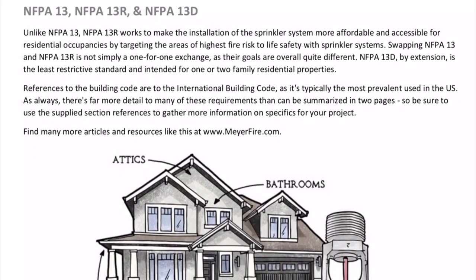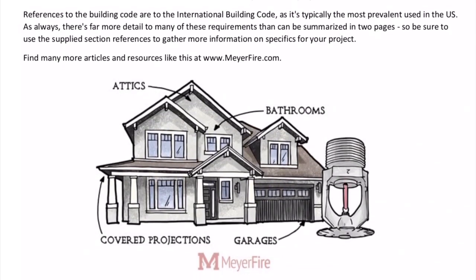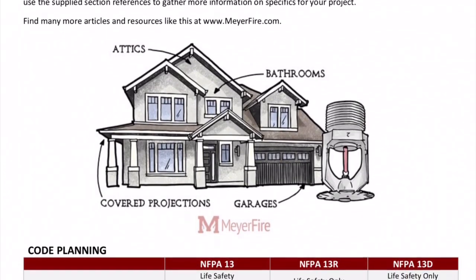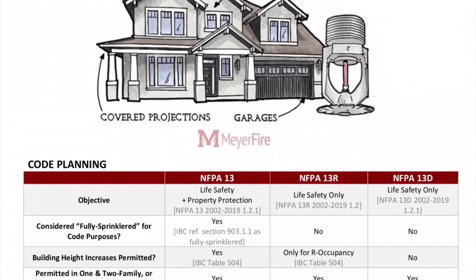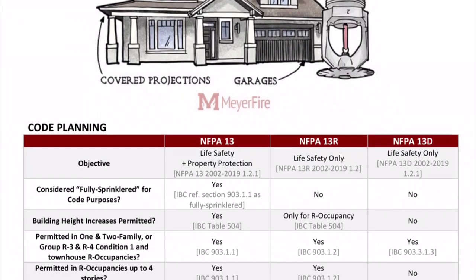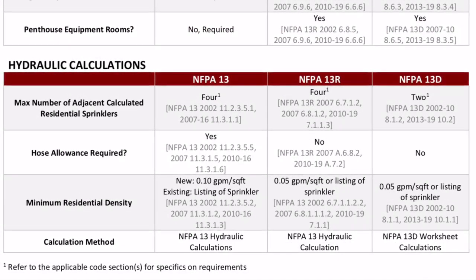Unlike NFPA 13, 13R works to make the installation of the sprinkler system more affordable and accessible for residential occupancies by targeting the areas of highest fire risk to life safety with sprinkler systems. Swapping NFPA 13 and 13R is not simply a one-for-one exchange, as their goals are overall quite different. NFPA 13D, by extension, is the least restrictive standard and intended for one- or two-family residential properties. References to the building code are to the International Building Code, as it's typically the most prevalent used in the U.S. As always, there's far more detail to many of these requirements than can be summarized in two pages, so be sure to use the supplied section references to gather more information on specifics for your project.